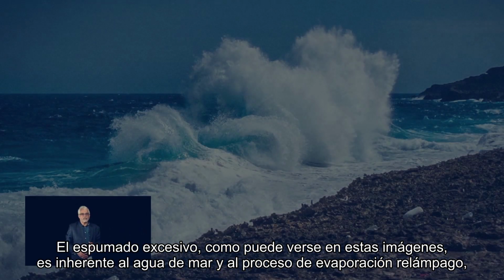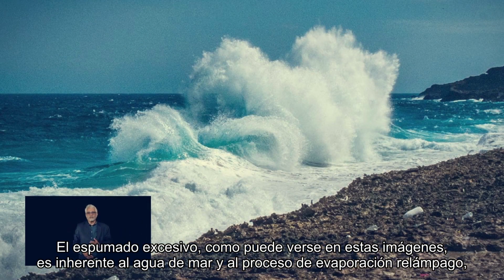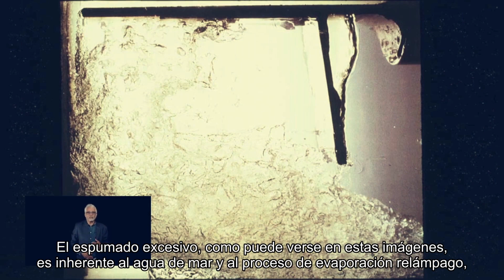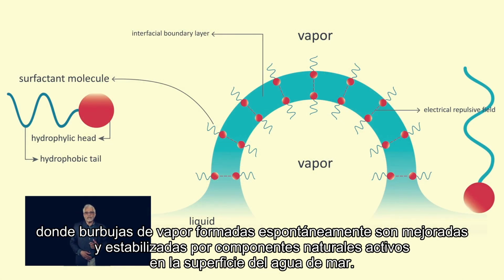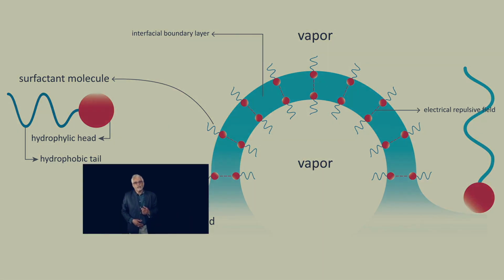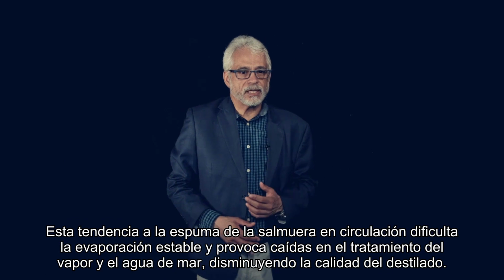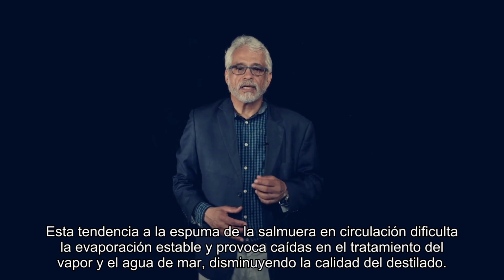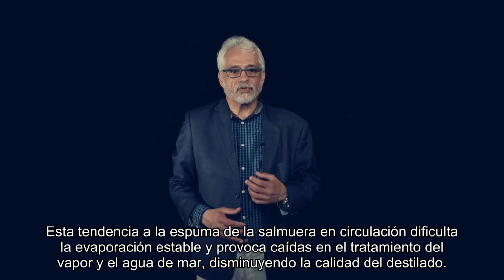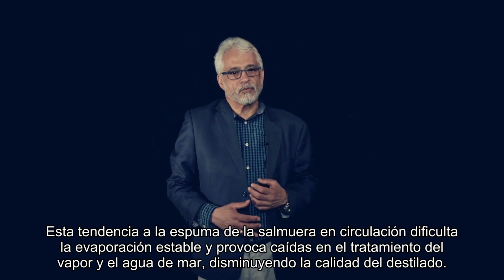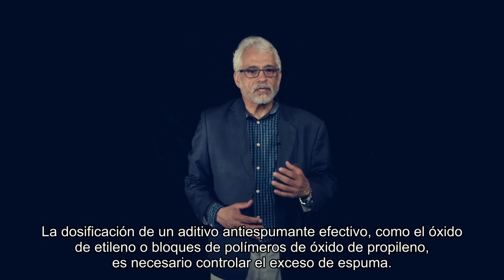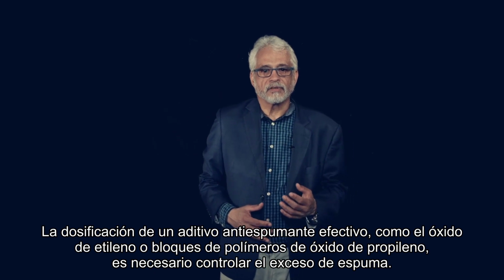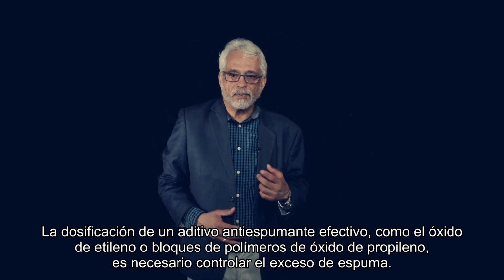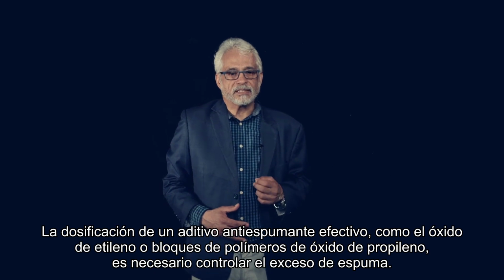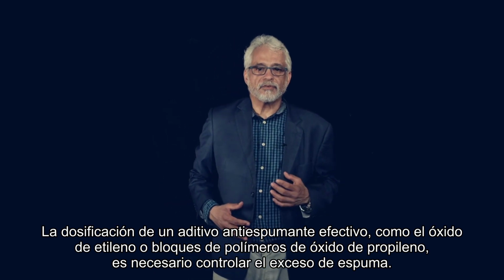Excessive foaming, as indicated in these pictures, is inherent to seawater and the flashing process, where spontaneously formed vapor bubbles are enhanced and stabilized by natural surface active components in seawater. This foaming tendency of the recirculating brine hampers stable evaporation and causes vapor entrainment of seawater droplets, which diminishes distillate quality. Dosing of an effective anti-foam additive, such as ethylene oxide propylene oxide block copolymer, is necessary to control excessive foaming.